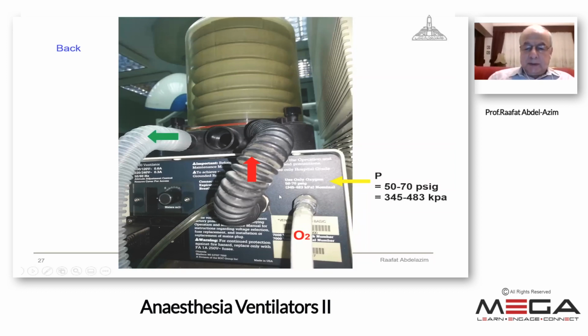The output, that is the tidal volume, will come into the hose, coming inside the chamber containing the bellows to compress it down to push the contents of the bellows into the inspiratory limb of the breathing circuit into the patient's lung.